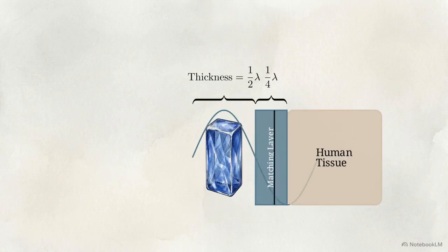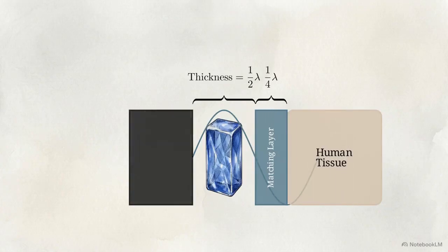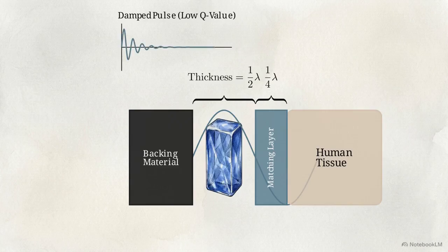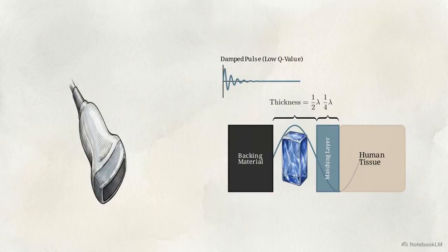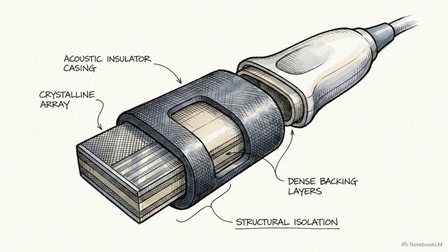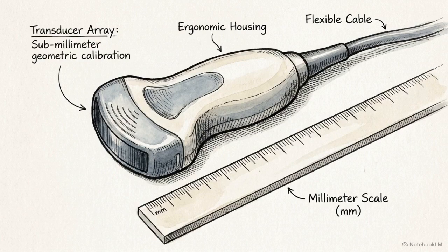Looking at the rear of the array, a dense block called the backing material sits directly behind the crystals. When an electrical pulse fires, the crystal vibrates. The backing material absorbs backward-moving energy, preventing it from reverberating and returning into the crystal. This physical dampening directly determines the array's Q value, abruptly stopping the vibration to control the exact length of the emitted ultrasound pulse. Finally, an acoustic insulator wraps the internal assembly, preventing these intense microvibrations from transferring into the operator's hand. The transducer is a tightly constrained acoustic engine. Its sub-millimeter geometric calibration dictates the efficiency of the entire imaging system.